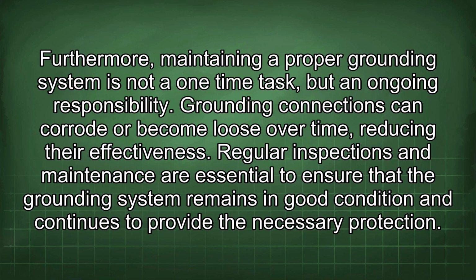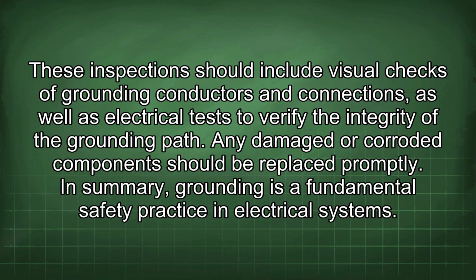Furthermore, maintaining a proper grounding system is not a one-time task but an ongoing responsibility. Grounding connections can corrode or become loose over time, reducing their effectiveness. Regular inspections and maintenance are essential to ensure that the grounding system remains in good condition and continues to provide the necessary protection. These inspections should include visual checks of grounding conductors and connections, as well as electrical tests to verify the integrity of the grounding path. Any damaged or corroded component should be replaced promptly.